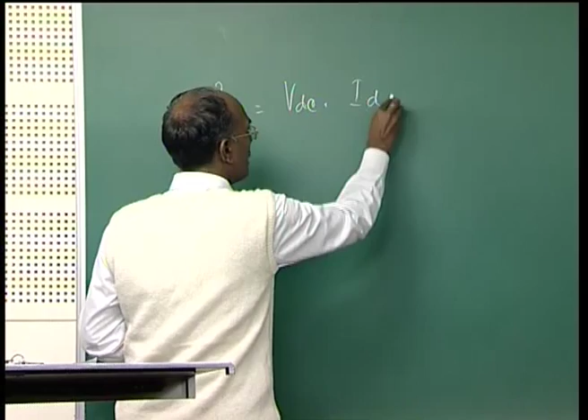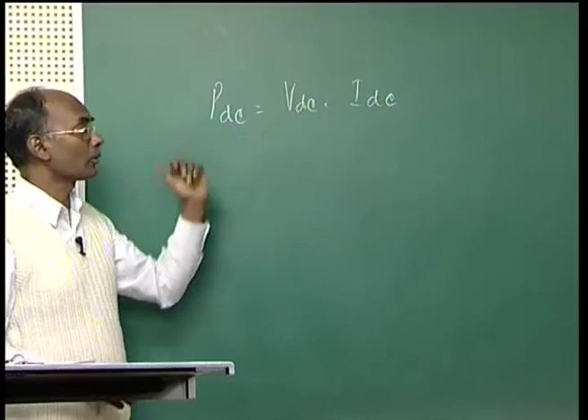For active power control, the DC power, that is PDC, can be calculated by multiplying the direct current and the direct voltage. It is very well known in either the conventional HVDC system, the HVDC Light, or the VSC based HVDC transmission system. The DC power is nothing but P equal to VDC multiplied by IDC. So whenever you want to control the power, you can control one of these quantities or both of them, and then you can control the PDC.